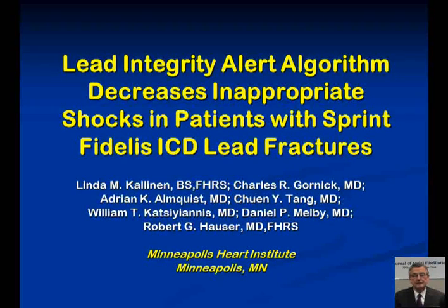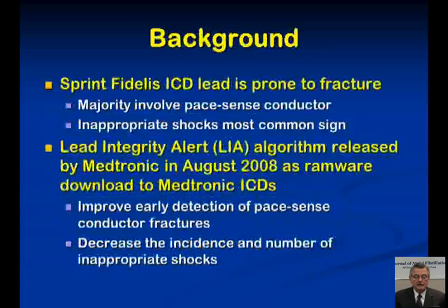Our paper today is "The lead integrity alert algorithm decreases inappropriate shocks in patients with Sprint Fidelis ICD lead fractures." The Sprint Fidelis ICD lead is prone to fracture, as all of us now know. The majority of these fractures involve the pace sense conductor, and inappropriate shocks are the most common sign of pace sense conductor fracture.